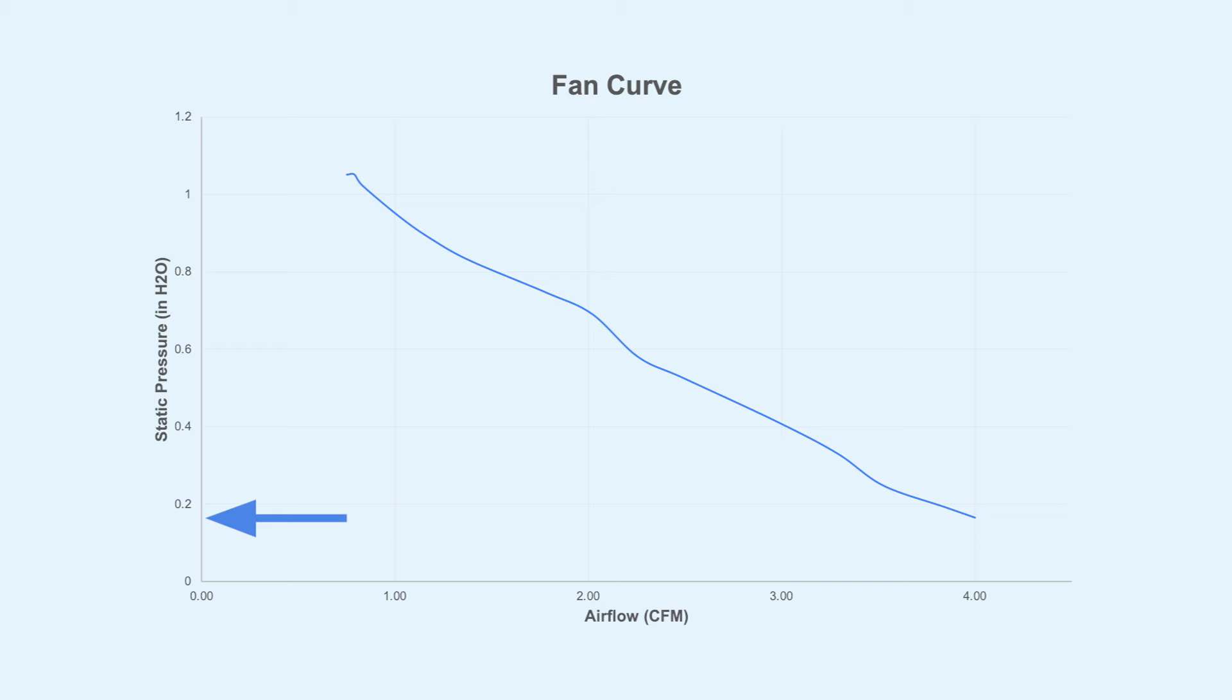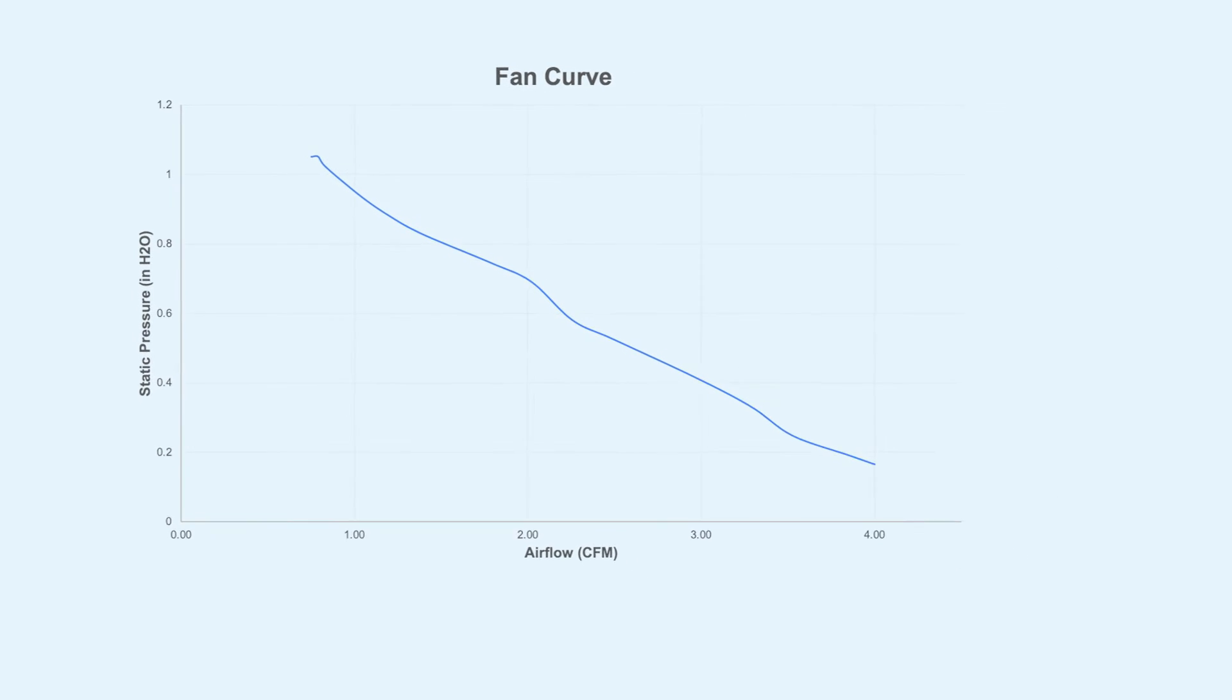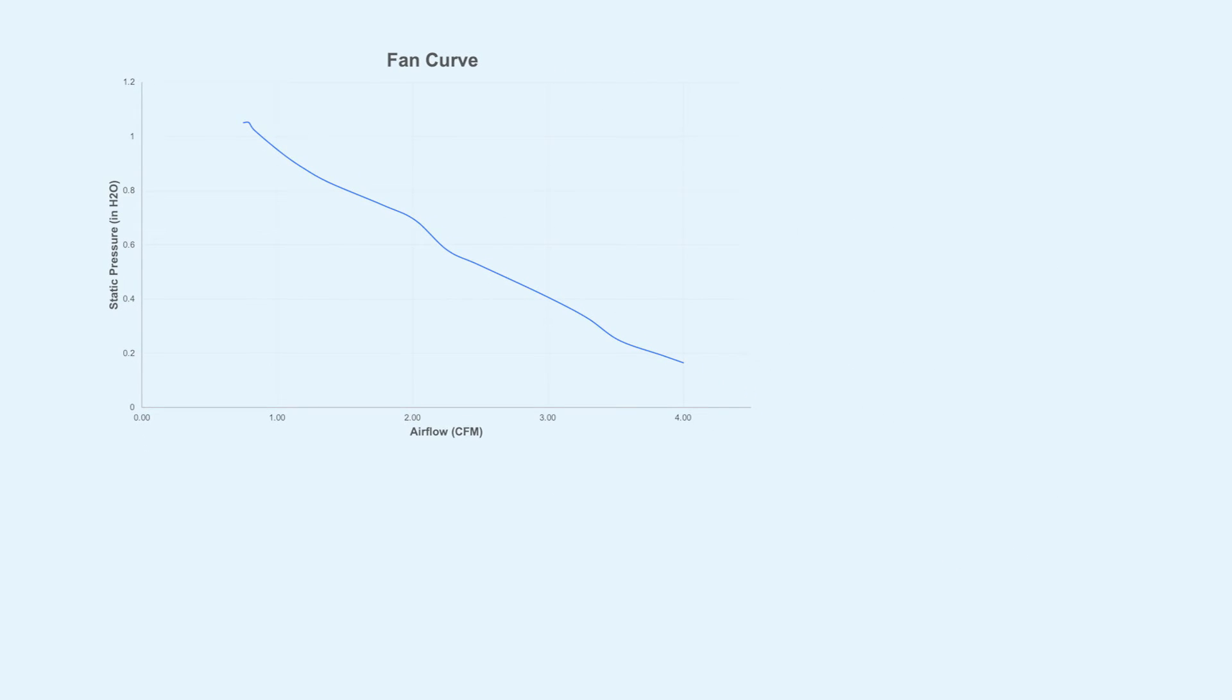And so that's where we need to go back to the fan curve to get our answer. So let's say now the resistance increased to 0.4 inches of water. How much air will the fan blow? Well according to our curve it's going to blow 3 CFM. And what if now the static pressure increased to 0.8 inches of water? Well now our airflow will decrease to 1.5 CFM.